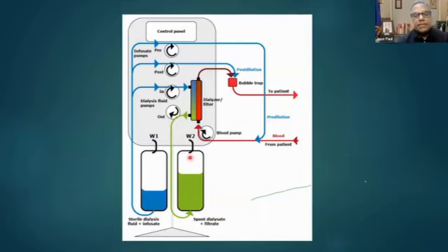As I already told, the principle that is used is hemodiafiltration. You run in the dialysis solution, you take out the fluid, and you run in a substitution fluid. So this is how the substitution fluid is run in.